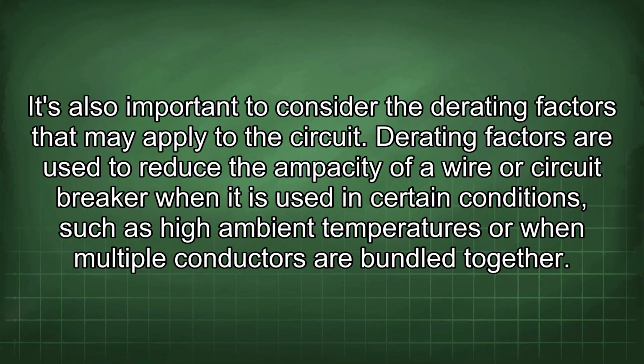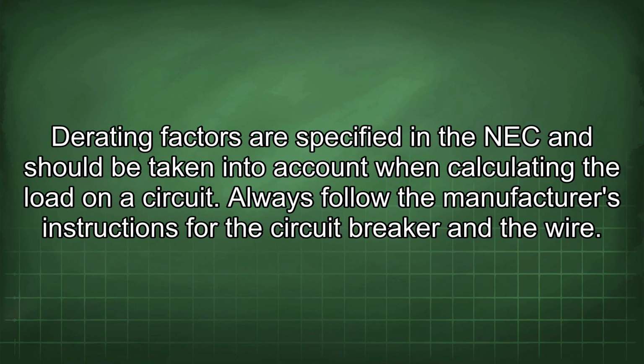It's also important to consider the derating factors that may apply to the circuit. Derating factors are used to reduce the ampacity of a wire or circuit breaker when it is used in certain conditions, such as high ambient temperatures or when multiple conductors are bundled together. Derating factors are specified in the NEC and should be taken into account when calculating the load on a circuit.